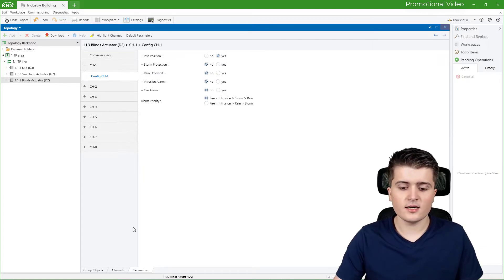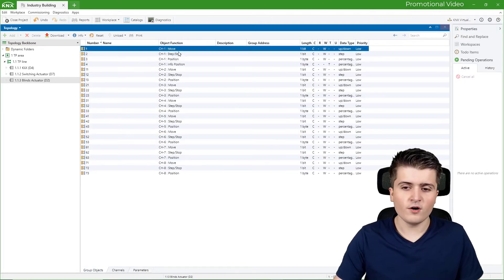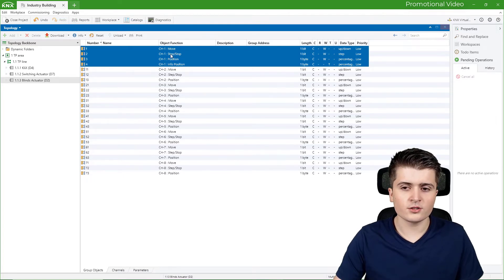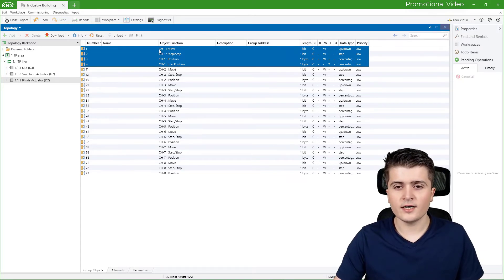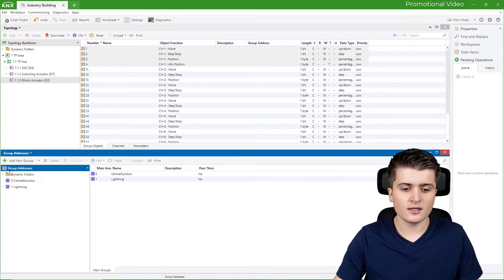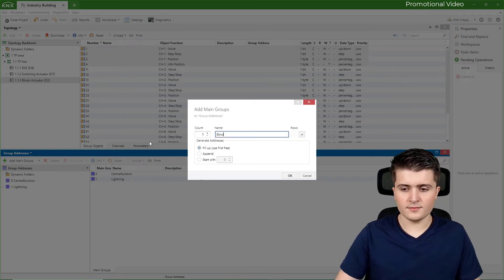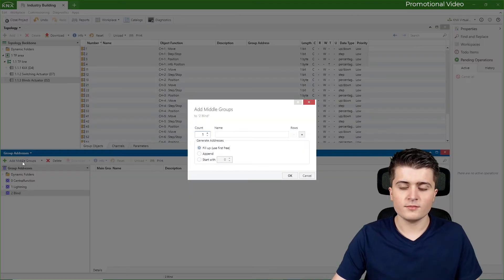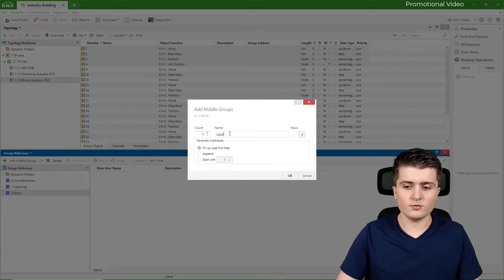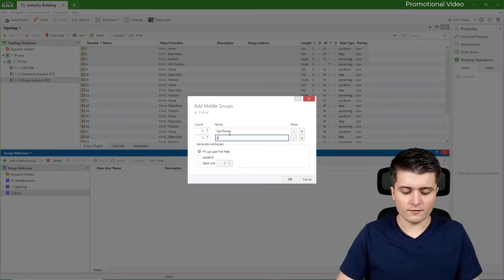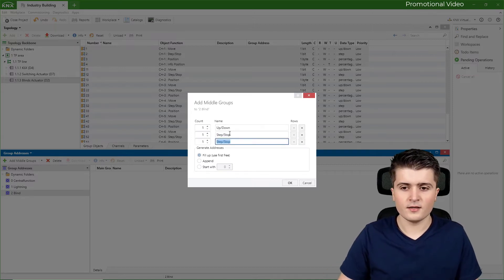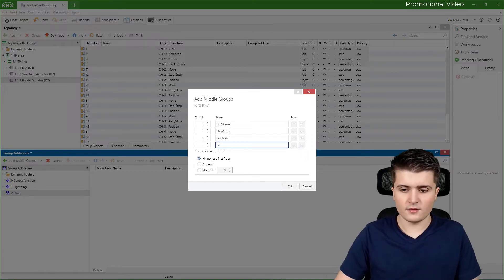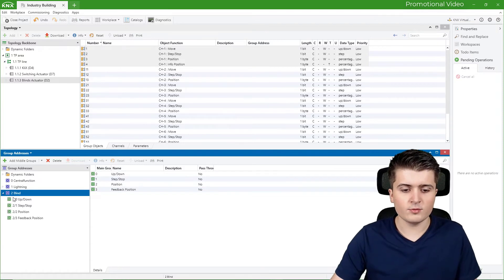Now that the blind actuator is set up, let's look at the group objects — we now have four for channel one: move, step/stop, position, and feedback position. Let's create the group addresses. I open the workplace, go to group addresses, and add a new main group called 'Blind'. Inside it I create four middle groups: 'Up Down' for movement, 'Step Stop' for stop and slat control, 'Position', and 'Feedback Position'.